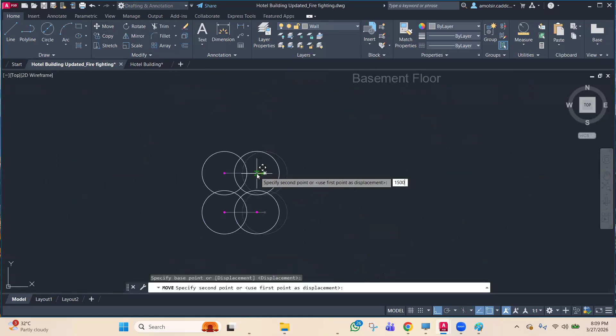So, sir, we have to check the maximum efficiency by the drawing, or is there some formula? No, there is no such formula. The maximum distance should not go beyond 15 feet. The minimum should not go below 7.5 feet. You can take any distance between them according to the design criteria. I will explain that also. Okay, roughly we should take 3 meter sprinkler to sprinkler? Yes, correct. So you can take the sprinkler to sprinkler distance as 3 meter, 3000 mm accordingly.